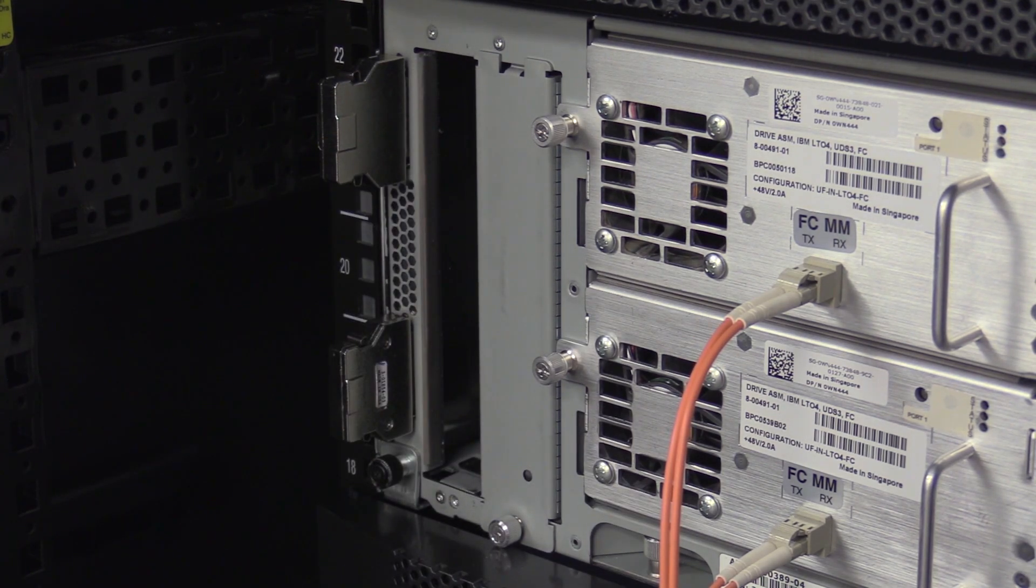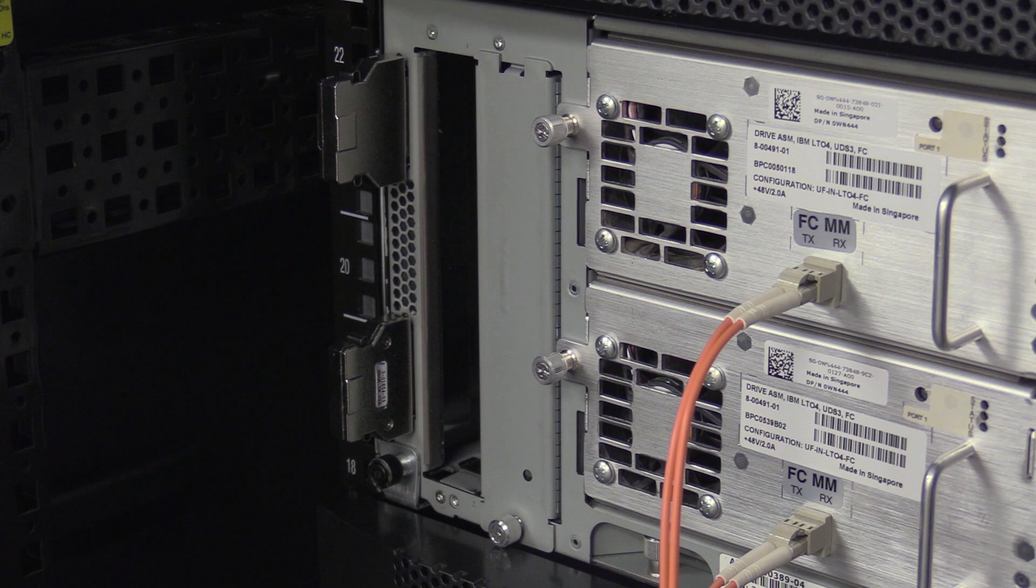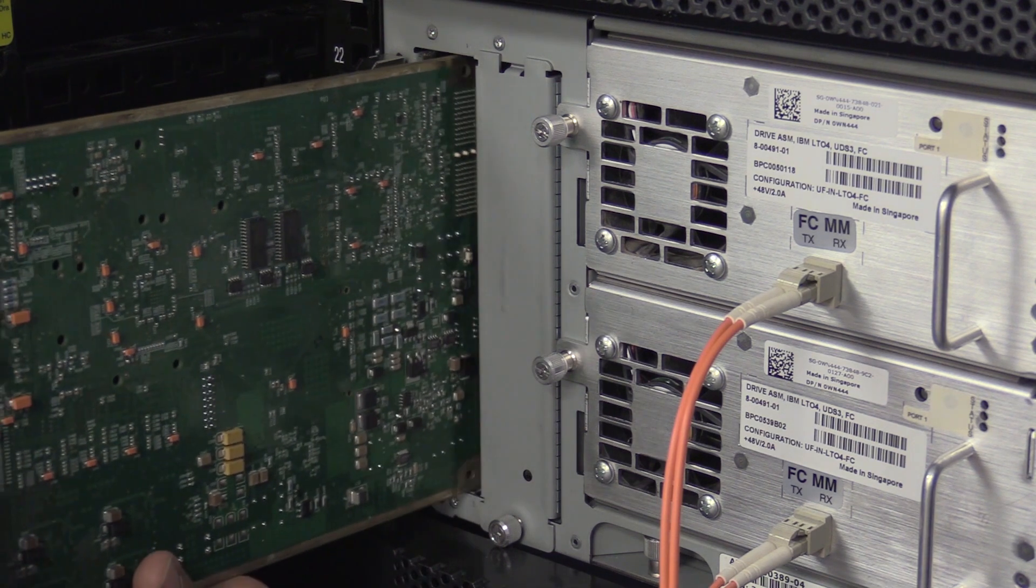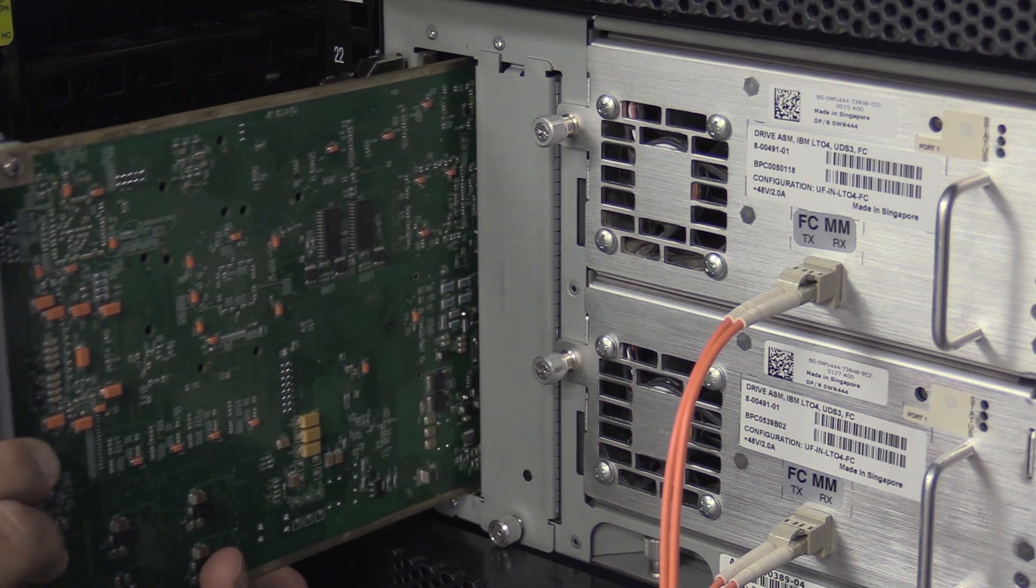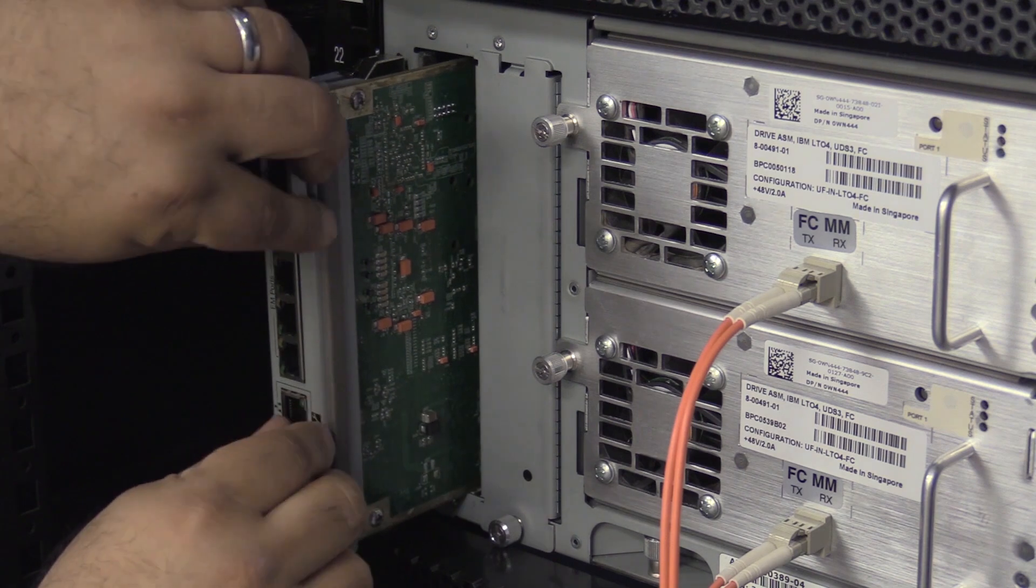You are now ready to insert the replacement control card. Line the replacement card up into the small rails in the control card channel where you just removed the faulty control card from. Push the card in approximately halfway until it is being held completely by the library.